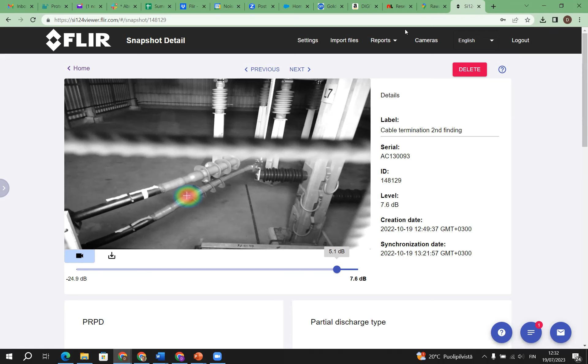Actually, they bought the camera a week before, and the camera was totally right, and not only found this one but also found, with the same conditions, this other partial discharge, which is even more severe, very high, or high to very high. They were quite worried, saying they hadn't included this end of the building, of the substation, and this might create a big problem if they don't take action soon. That's why I say qualification and analytics, the severity and the recommendations, are very important for the customer.